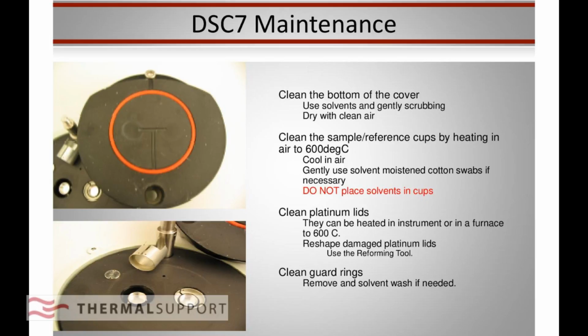We like to take them in and out with the sample manipulators, and then take the guard rings out, and you swish them around in a solvent. Some people use a little Q-tip. My preferred method of what we do here is that we've got an ultrasonic cleaner. If you got one of those, just put a mild solvent in there that's going to attack the sample that you got. Drop it in there and clean it ultrasonically. It works fantastic. That's probably the best way to do it. And then put everything back together, do yourself a cleaning run, and you're ready to go.